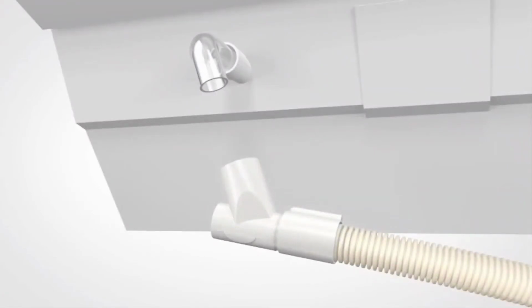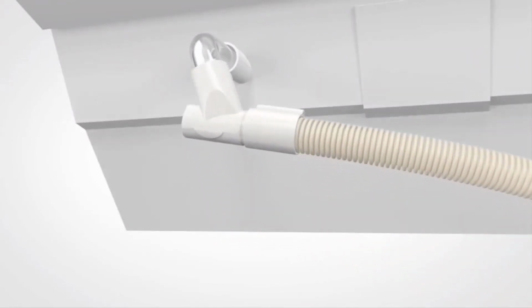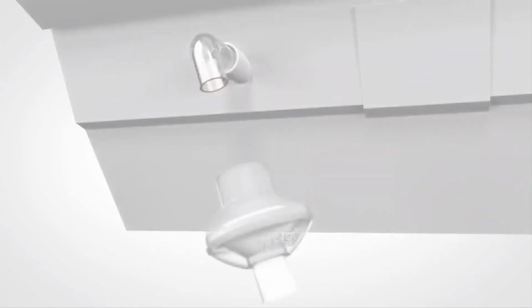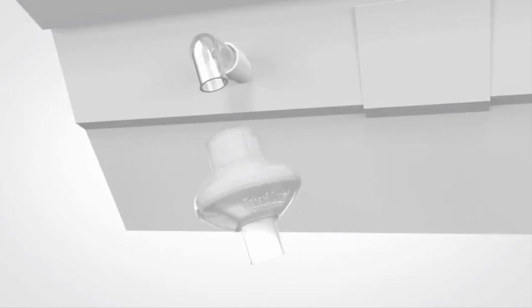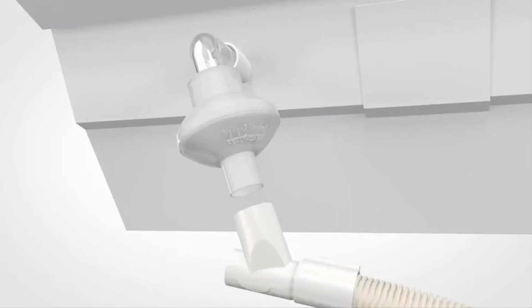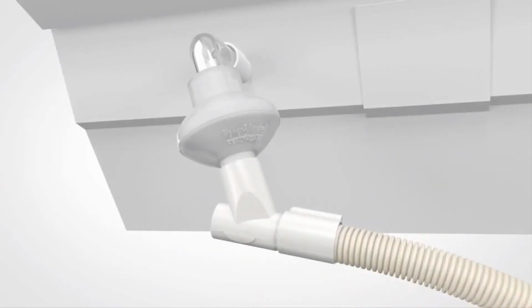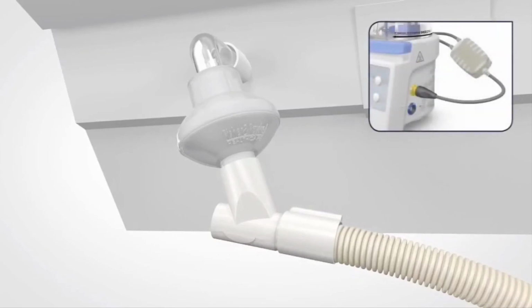Connect the ventilator end of the expiratory limb to the expiratory port on the ventilator. If you are using an expiratory filter, connect it between the expiratory port of the ventilator and the expiratory limb. For dual limb applications, the heater wire adapter will have two circuit leads.